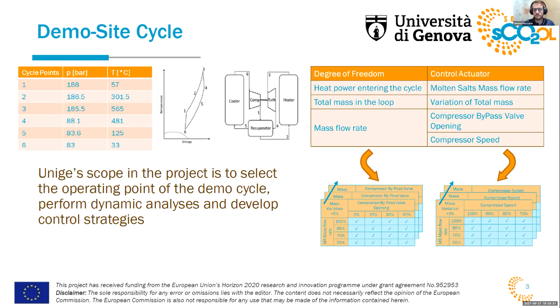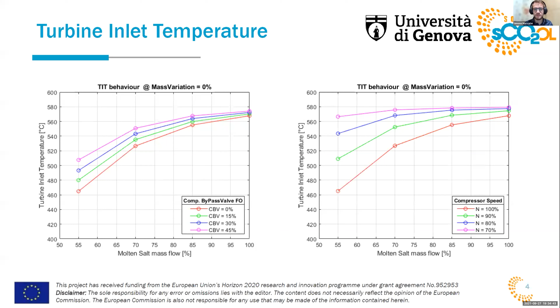I want to show you some very basic results from these analyses. Here is the variation of the turbine inlet temperature at a mass variation of the cycle at 0%, so with constant mass inside the cycle. We can see there is a decrease in the turbine inlet temperature, which strongly affects the behavior of the whole cycle. On the left side you can see the variation of the fractional opening of the compressor bypass valve, and on the right side the variation of the compressor speed. Of course all is non-dimensionalized on design values, using the pre-designed values of all the components given from the partners. These are the first main results.